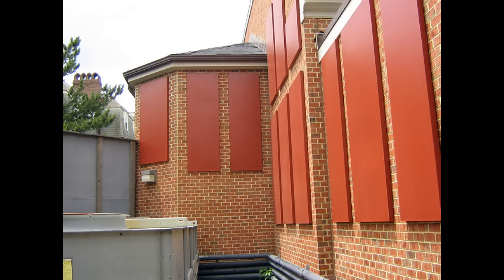It's also going to help with the vibration and the sound going into the building itself, probably to some degree. And I'm very certain those are perforated metal panels that have probably acoustic fiberglass mat on the inside, or possibly mineral wool sometimes is used.